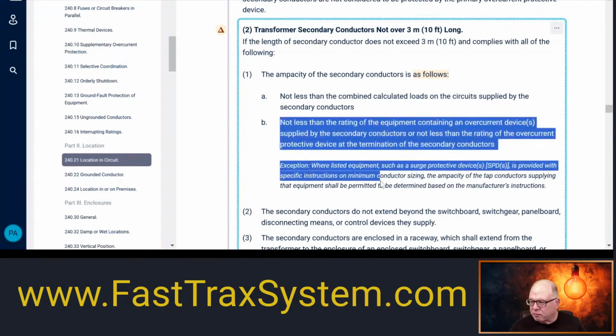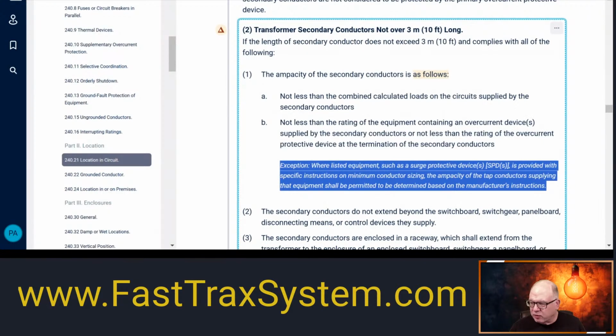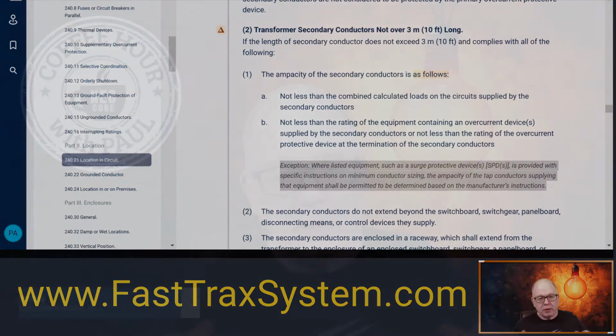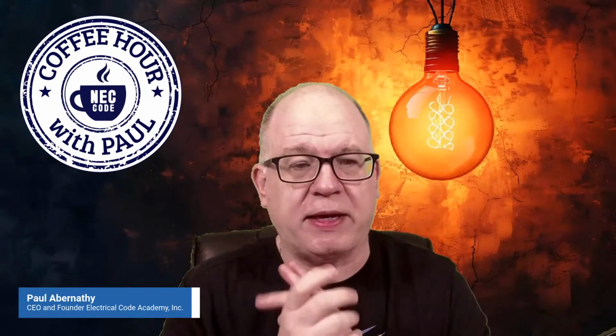So this is where you may have some special equipment, okay? And even they say the word tap in here, right? They have some special equipment which may come with the manufacturer's requirements, and manufacturers may be more restrictive than, let's say, the National Electrical Code. Typically, we hope most of the time, the manufacturers will be equal to the NEC, but there are some occasions where they are more restrictive. And if they're more restrictive, you follow the manufacturer. If the manufacturer is less restrictive than the NEC, then you contact the manufacturer and then work with your AHJ, because, again, we don't know if that equipment maybe was made overseas. We don't know what kind of testing. We will hope that it's tested by an NRTL, nationally recognized testing laboratory, where applicable.